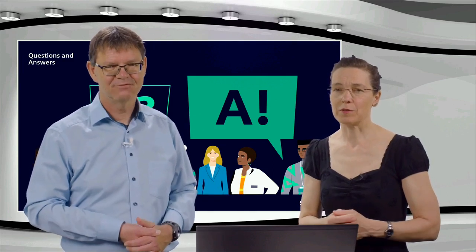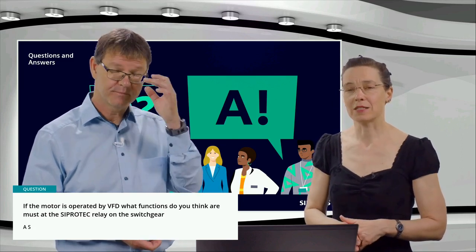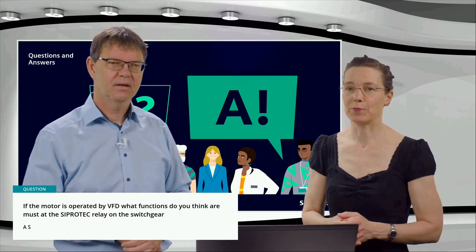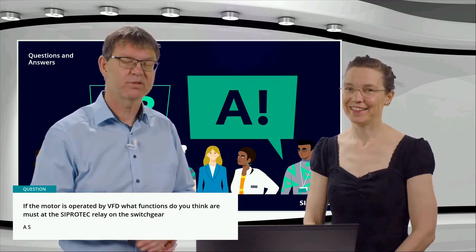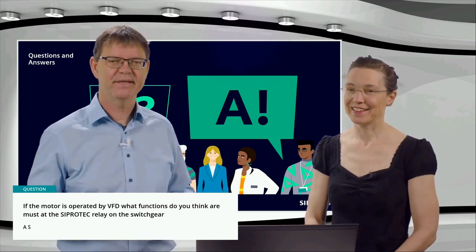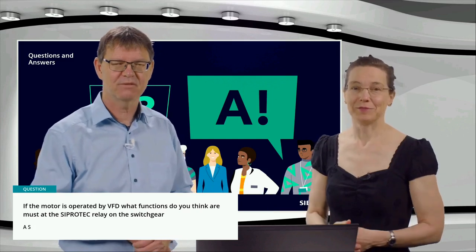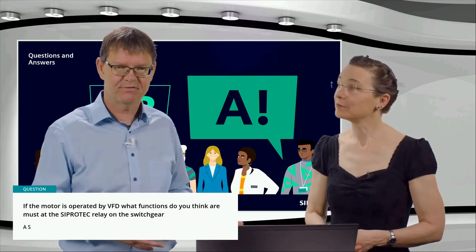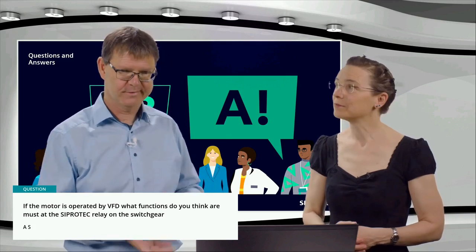One fresh question just came in. If the motor is operated by a variable frequency drive, VFD, what functions do you think are a must in the SIPROTEC relay on the switchgear? This basically depends on what the VFD provides as protection functions, so I cannot give a general answer. If all the functions are already in the VFD, then you don't need the protection device. If it's a big motor, maybe the differential protection, if it's not part of the VFD. What I could imagine could then be a dedicated protection function for the SIPROTEC device.